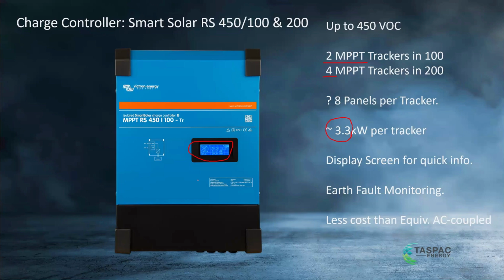Might be a dangerous thing for your customer, but it's actually quite good to look at that, either directly or even better on the VRM portal. You can then judge if there's a problem with one of the arrays, or some shading, or the panels are dirty. It's likely both arrays will get dirty at once, but there's a fair bit of handy information there. It's also got built-in earth fault monitoring that makes it compliant because it's above ELV.